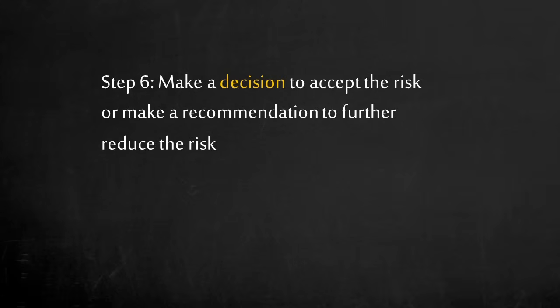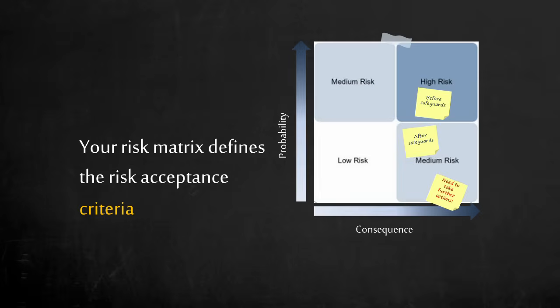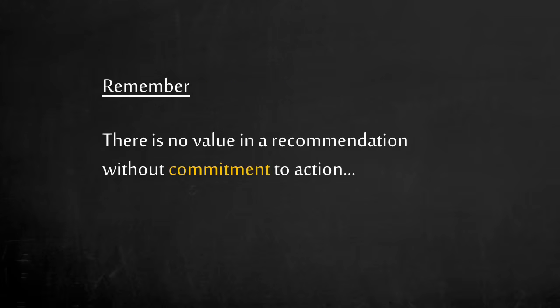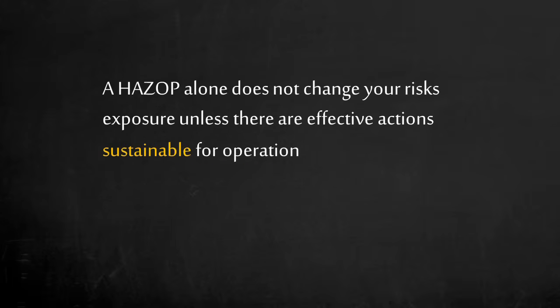Step 6: The final step is to make a decision to accept the risk or make a recommendation to further reduce the risk. By lowering the probability using a safeguard, the risk is lowered. Your risk matrix defines the risk acceptance criteria. Depending on the risk, you may need to make a recommendation when the risk is not acceptable. Remember, there is no value in a recommendation without commitment to action. It is important that each recommendation gets buy-in from both engineering and operations. A HAZOP alone does not change your risk exposure unless there are effective actions sustainable for operation.